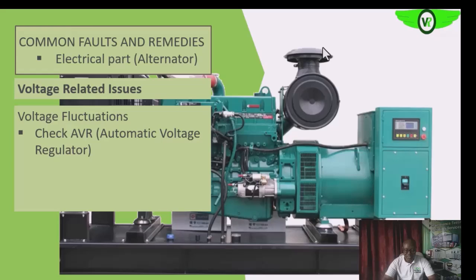If the AVR is delivering inconsistent current to the exciter field, it means the field will be producing and decaying, causing fluctuation of the magnetic field in the main field. That will eventually cause fluctuation of what is induced into the main armature. Also check the diode rectifier plate — if it is shorted, instead of rectifying it will deliver AC voltage to the main field, causing voltage fluctuation.